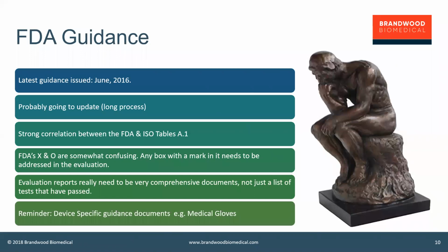Not that ISO has followed FDA slavishly, in no way could that be claimed, but certainly the two documents now align quite well. And FDA still maintain their X's and O's, which is somewhat confusing, but essentially any box with a mark in it in the FDA guidance table A1 needs to be addressed in the evaluation. And this quite well aligns with the ISO table A1 and the need to evaluate everything with an E in it from that table. And evaluation reports really need to be very comprehensive documents.